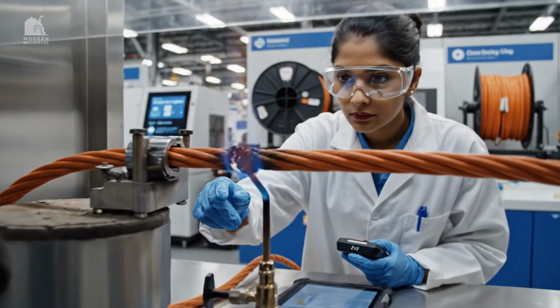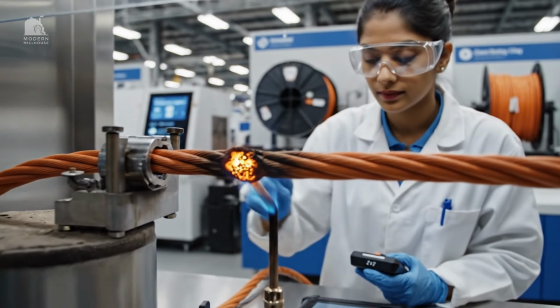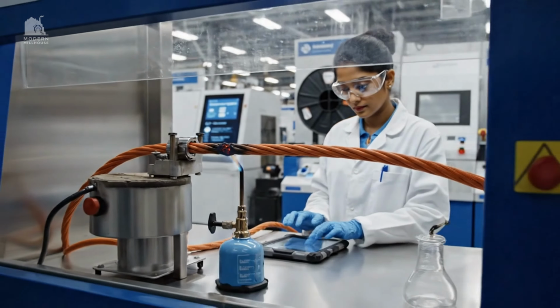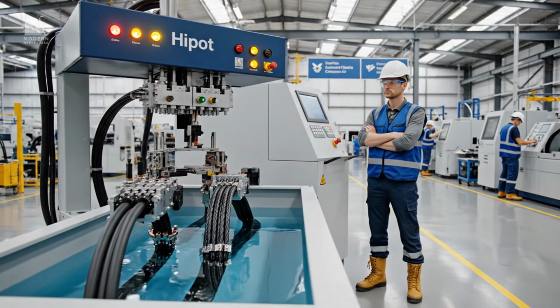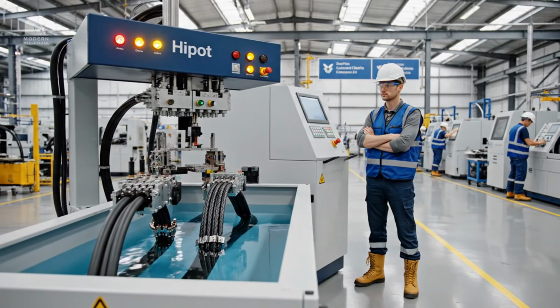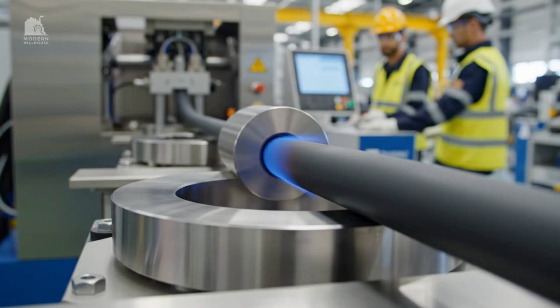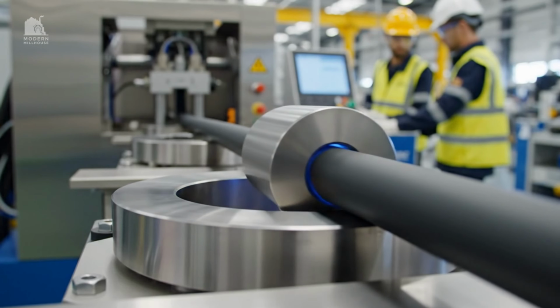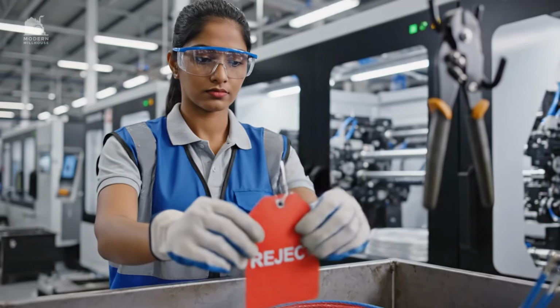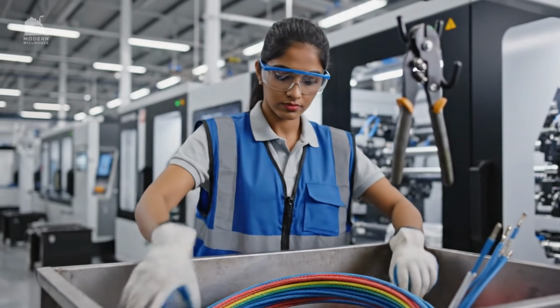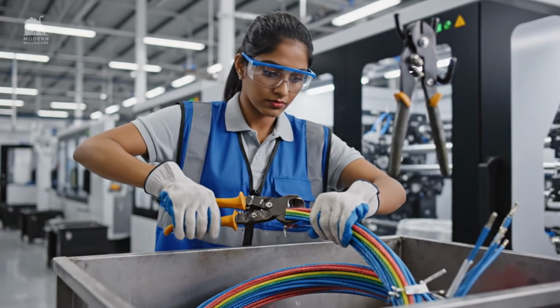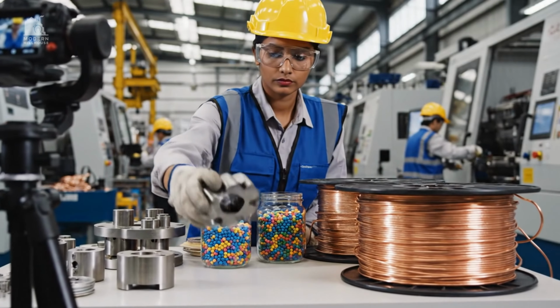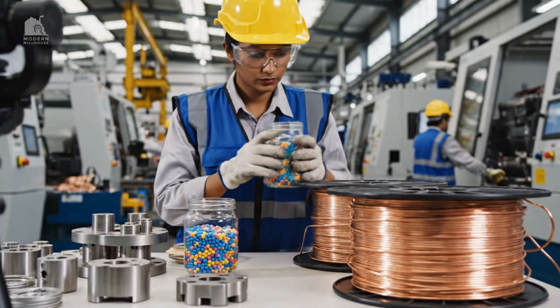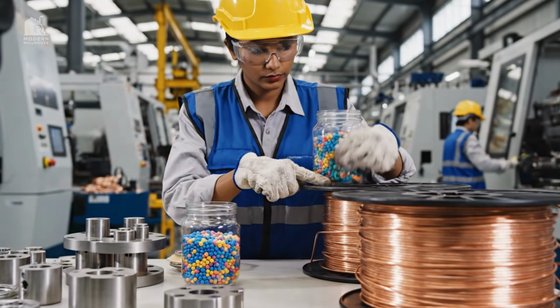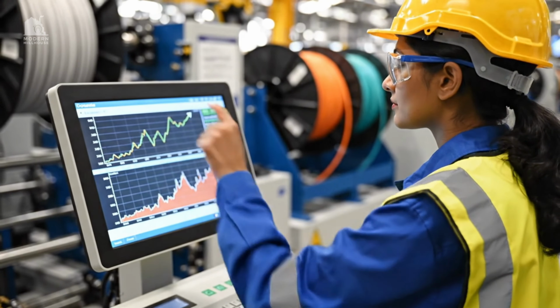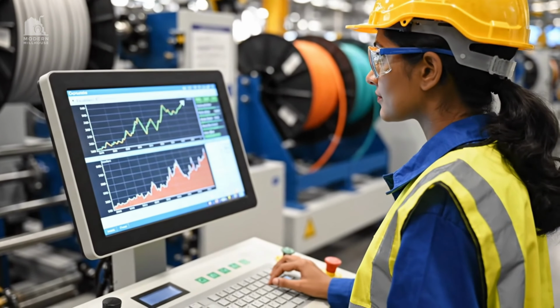Flame behavior matters in buildings, so compounds are chosen to resist spread and self-extinguish. High voltage withstand tests confirm the insulation can resist breakdown at its rated voltage. Spark testing after jacketing catches any damage introduced during cabling and handling. If anything fails, the product is isolated and investigated, protecting downstream customers. Investigations trace defects to specific causes: die centering, contamination, overheating, or tension spikes. Process data helps prevent repeats, turning testing results into tighter control on the production floor.